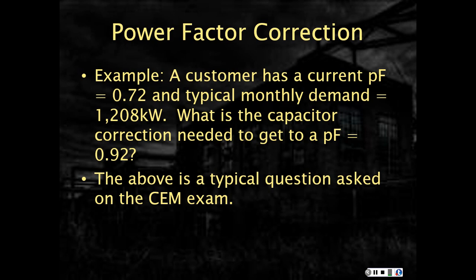Let's take a look at power factor correction. I have a customer that currently has a power factor of 0.72, and with most utility companies, that 0.72 will be in the penalty area of power factor. The same customer at the same time has a monthly demand of 1,208 kW. What's the capacitor correction needed to get the power factor up to 0.92? So what the customer really wants is to add capacitors to his system to correct that 0.72 up to a 0.92. So he basically goes from a penalty phase into a bonus phase. The above is a typical question asked on the CEM exam, the Certified Energy Manager exam.